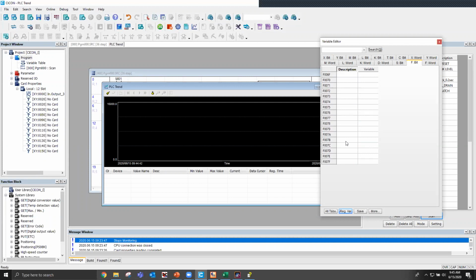If I go all the way to the 90s, which are my favorite, we have some embedded clock functions, so you don't have to make your own counters or timers. This one will be on for 0.01 seconds, 10 milliseconds, then off for 10 milliseconds. Another will be on for 50 milliseconds and off for 50 milliseconds—basically, cut the number in half: that's how long it'll be on, and that's how long it'll be off. This one will be on for 30 seconds, then off.